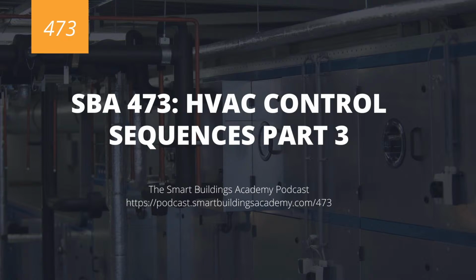Now, what we also learn is that utilizing that control, we can also just simply have a pre-programmed minimum position, and this works really well on constant air volume systems. It's a little wonky on variable air volume systems. But on constant air volume systems, where the air volume is constant and the fan's at a constant speed, we can set a minimum damper position for our CO2 and ASHRAE 62.1 control, because we always know how much air we're going to be pulling in via the airstream because we have a constant volume of air. When we're using variable air volume systems, that's where things get a little weird, and that's why we tend to have to use airflow stations in order to properly control.